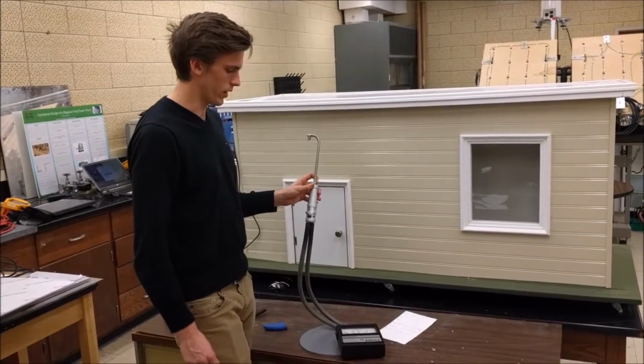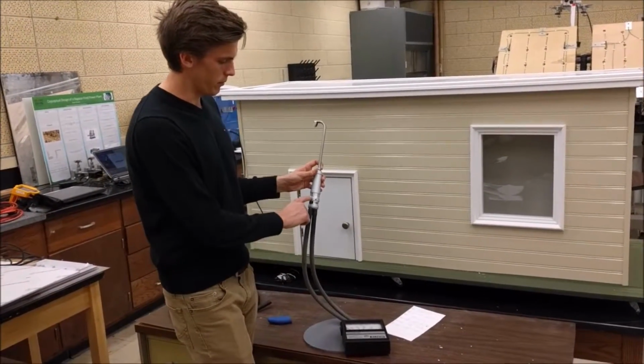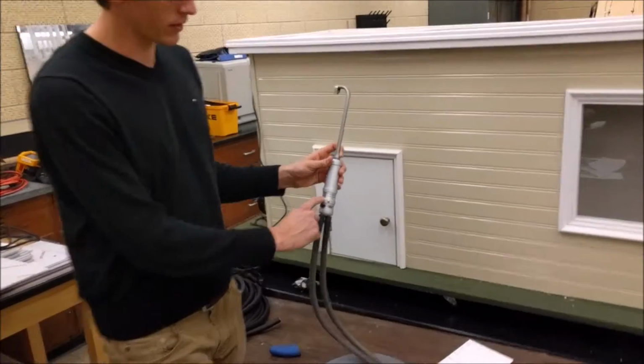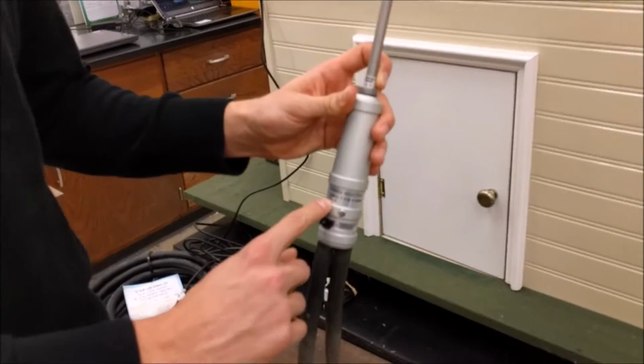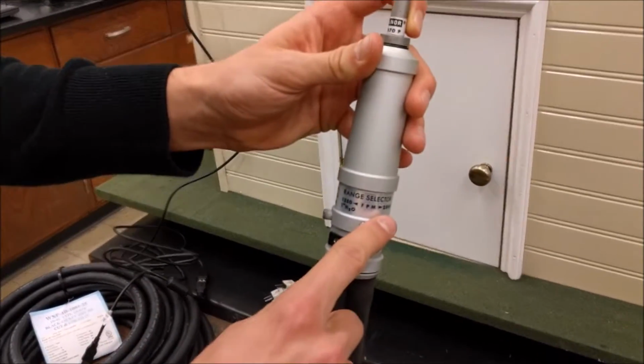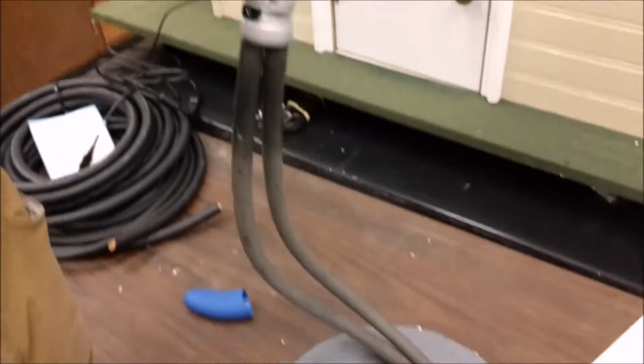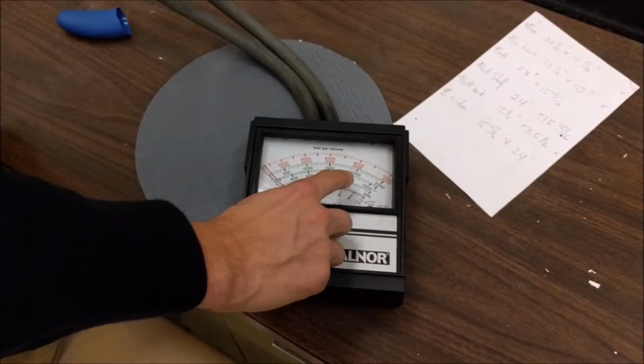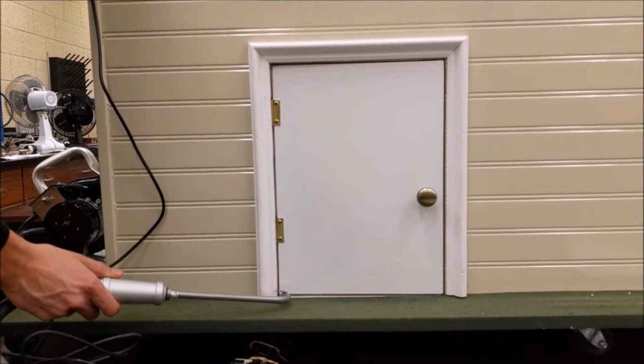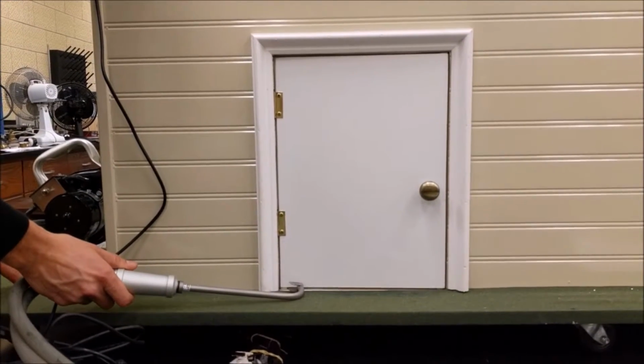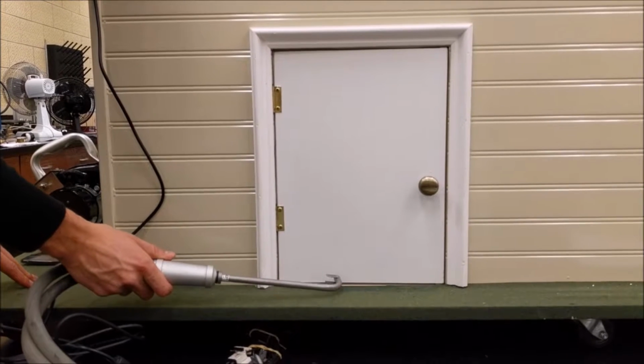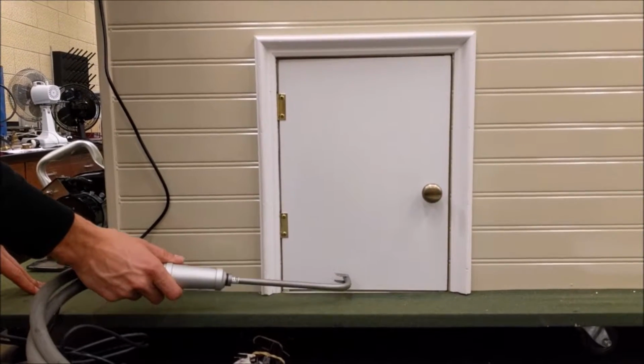At the 16-minute point, we will also be measuring the flow of air coming from underneath the door. Before recording data, note the different nozzles produce different readings, so make sure your nozzle range corresponds to the value range you're reading off of on the hub. To measure the airflow from under the door, take 4 readings, 1 close to the hinge, 2 close to the center, and 1 near the end of the door.